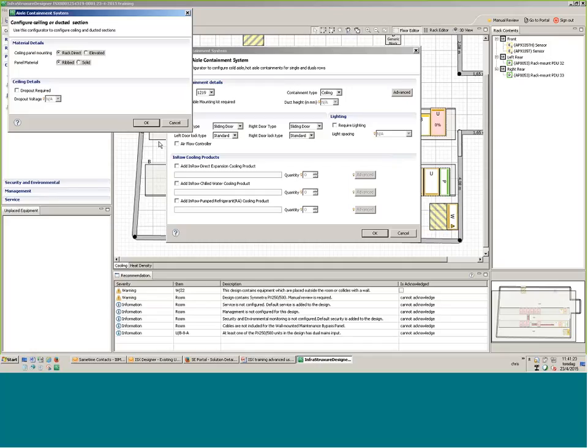Then we have the dropout required. So dropout is a possibility you can have if you have a fire extinguish system which needs to gas the room, or have as like a shower from top. So the dropout, if you reach a certain degrees of temperature, it will fall. It will give you a warning by siren and light, and then you have about 10 seconds. No, not about. You have exactly 10 seconds to leave the room or the hot aisle containment. Otherwise, it will fall on your top. And especially with the solid, it is quite heavy.